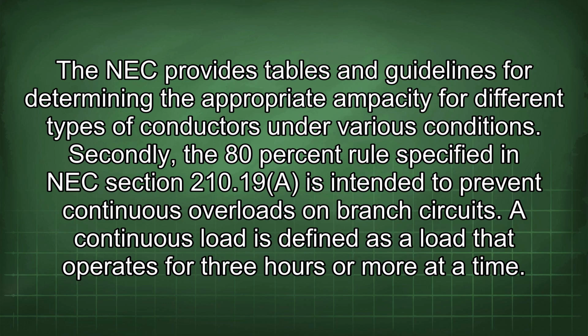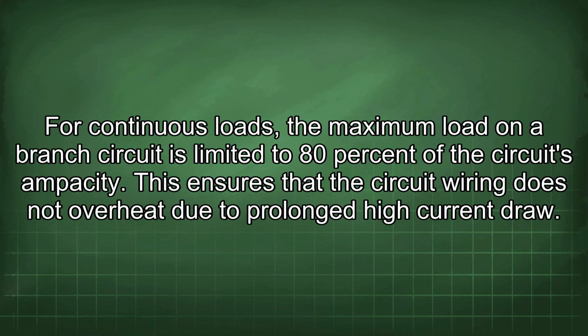Secondly, the 80% rule specified in NEC Section 210.19 is intended to prevent continuous overloads on branch circuits. A continuous load is defined as a load that operates for 3 hours or more at a time. For continuous loads, the maximum load on a branch circuit is limited to 80% of the circuit's ampacity. This ensures that the circuit wiring does not overheat due to prolonged high current draw.